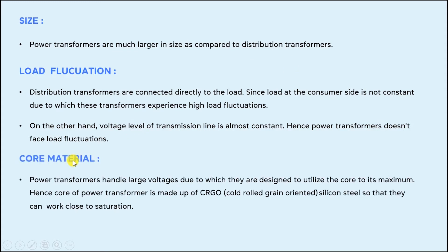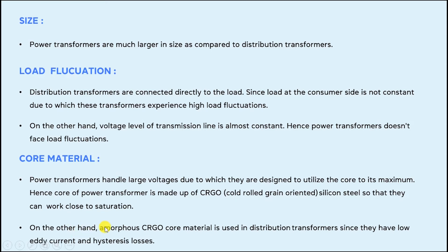The next point is the core material. Power transformers handle large voltages, so they are designed to utilize the core to its maximum value. The core of a power transformer is made of CRGO — cold-rolled grain-oriented silicon steel — so that they can work close to the saturation point. In distribution transformers, amorphous CRGO core material is used since it has no eddy current and hysteresis losses. Amorphous core material is not used in large transformers like power transformers due to its mechanical weakness.